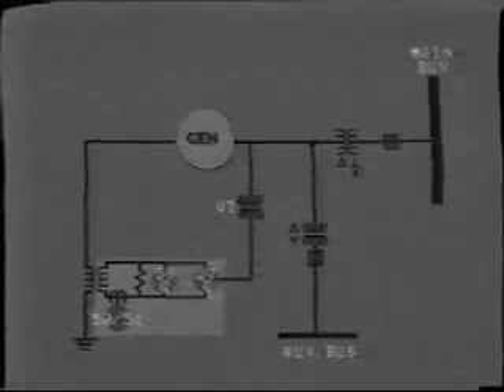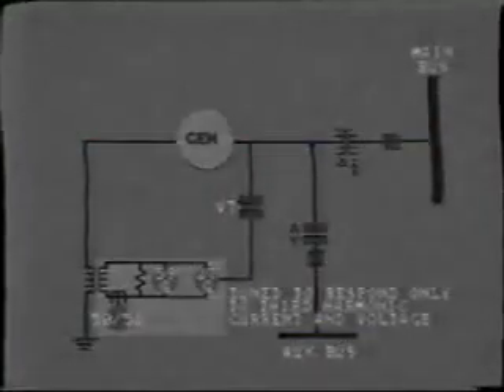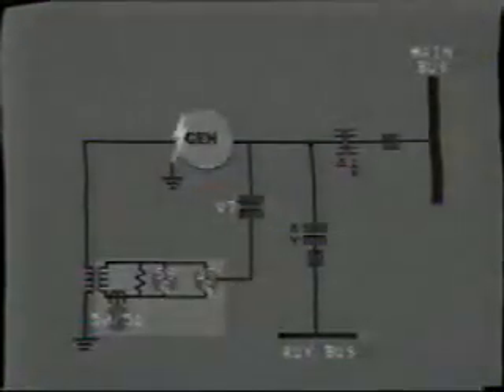In contrast to this, we may often encounter an undervoltage relay, 27G, which functions using the third harmonic. This relay is connected in parallel with the time overvoltage relay, 59G, and it is tuned to respond only to third harmonic currents and voltage. Under normal operation, where third harmonic voltage is present, this relay does not operate. Remember, it is an undervoltage relay. However, if a ground fault occurs in the generator windings close to the neutral, then these third harmonic components will be short-circuited, and the corresponding third harmonic voltage will be considerably reduced, thus operating the relay.